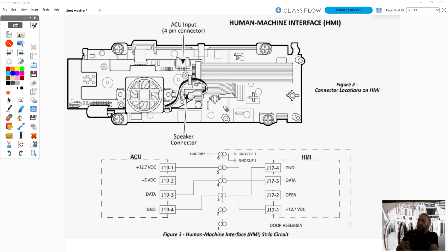Yeah, definitely, because you don't want to order the switch, it takes 2 or 3 days, then the customer takes off another day or a couple hours from work to meet you, and you put the switch in and it does not totally fix the machine. The switch could still be bad, but jumping it out will let you know that everything else in the machine is good, so you don't have to come back more than once.